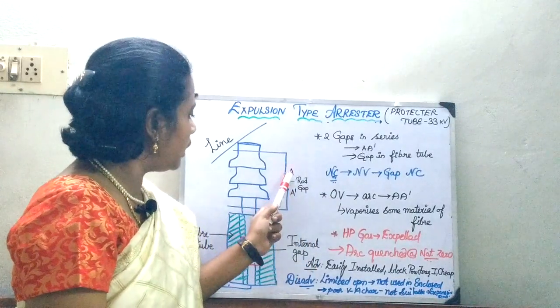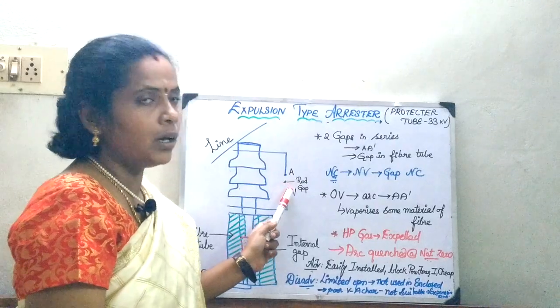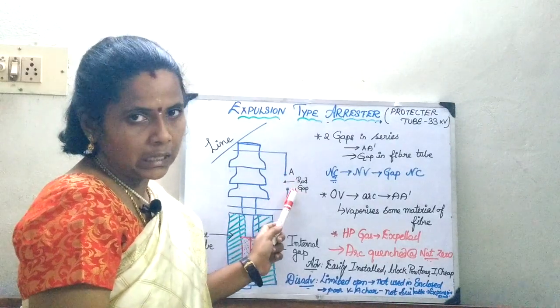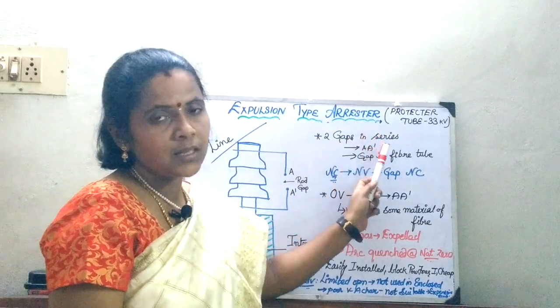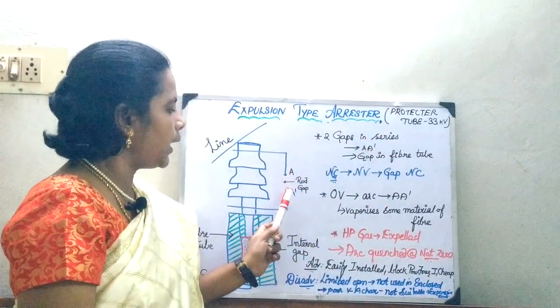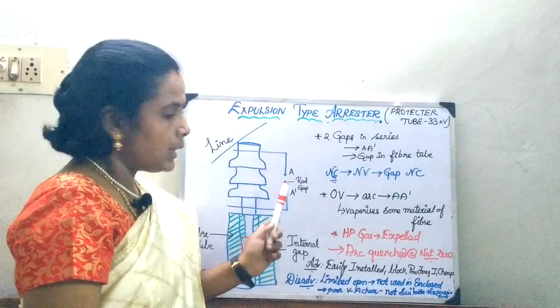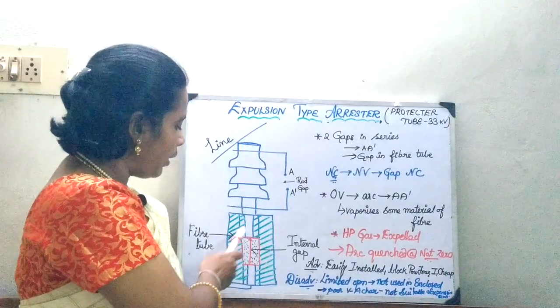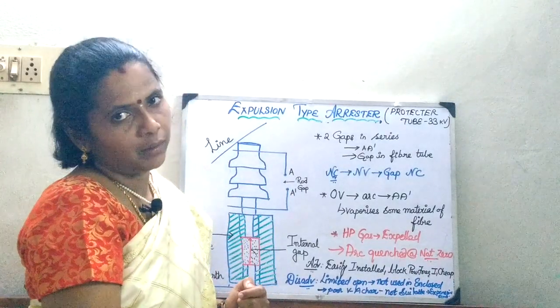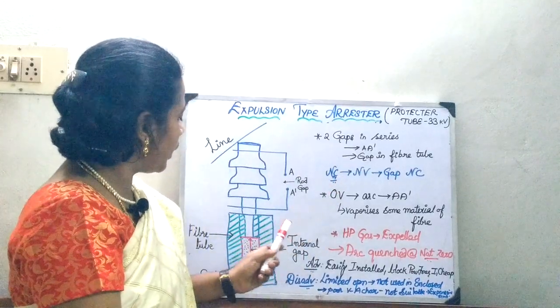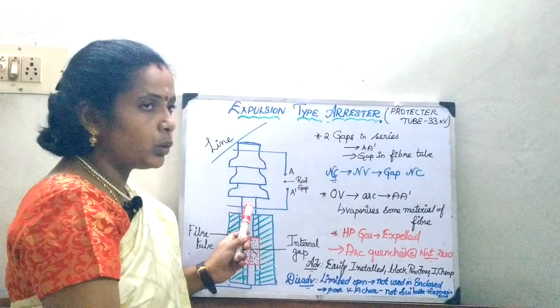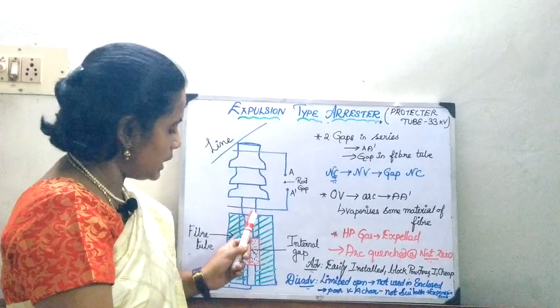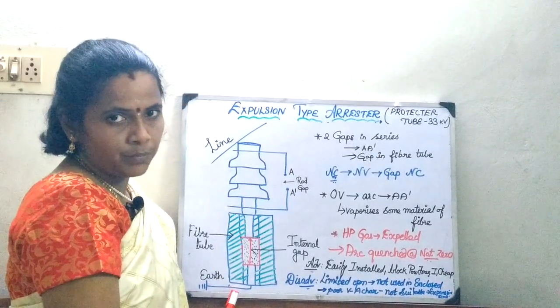In the earlier thing, you had only one spark gap in series. Now, you are going to have two gaps in series - one is going to be provided between this path A, A dash in your rod gap. The second path is going to be provided inside the fiber material. So the one end of the fiber is going to be connected to the rod, which is going to be in series, the other end is going to be earthed.